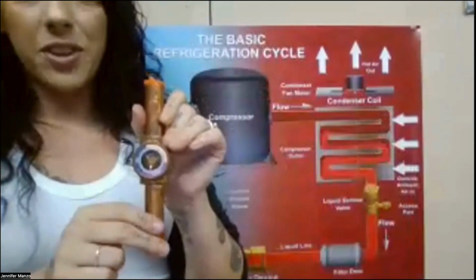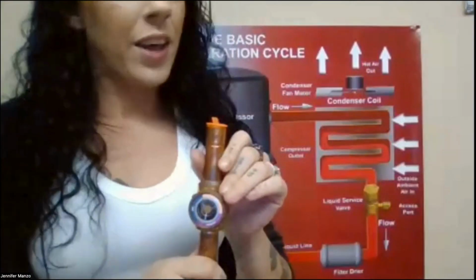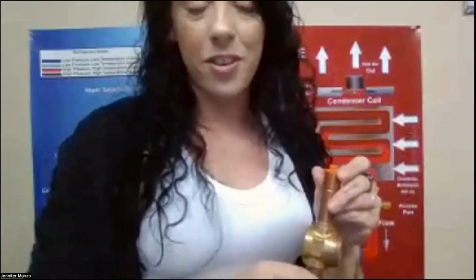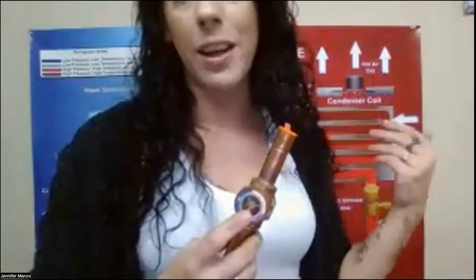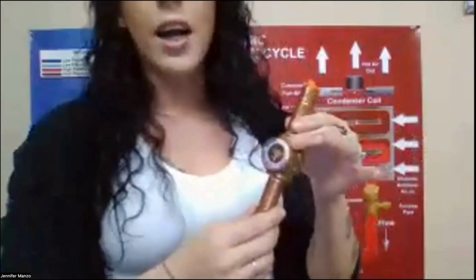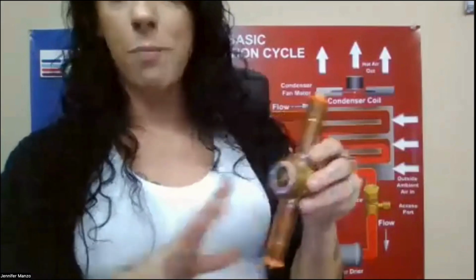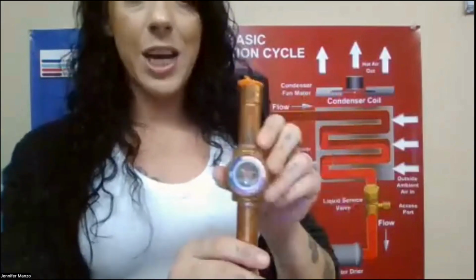This, mainly on commercial systems, I have seen a few residential systems that have them, but it's mostly because the installer didn't understand not to put one on a residential system. So you'll get what's called flash gas on a residential system, and you'll see it in the sight glass, and it will just confuse you and make you think your system is low, even though it isn't. But on commercial systems, I actually have a video if you guys want to check it out on the SkillCat TikTok, from probably last year or so, of the sight glass clearing.